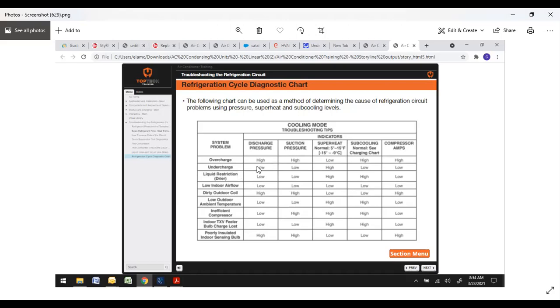Undercharge, similar. If you have a very low discharge pressure, a very low suction pressure, usually at that point your superheat's going to be extremely high because it's not cooling. Subcooling is going to be extremely low because it's not cooling. There's not enough refrigerant in the system. And the compressor amperage is going to be low because it's not working very hard to run. So usually undercharge is not always obvious, but a little more obvious.